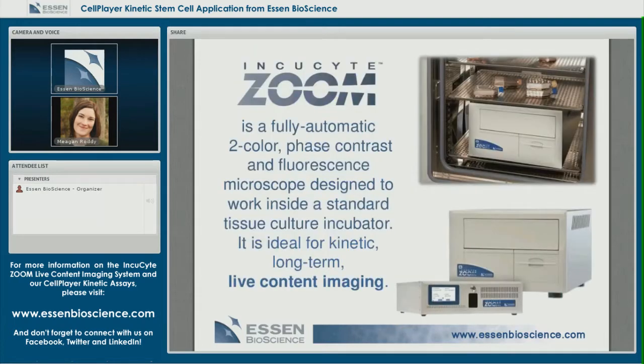The instrument we use to make live content imaging a reality is the IncuCyte Zoom. Zoom is a fully automatic two-color fluorescence plus phase contrast microscope that sits inside a standard tissue culture incubator. Because the cells being imaged in Zoom are within the tissue culture incubator, the design is ideal for kinetic long-term live content imaging.